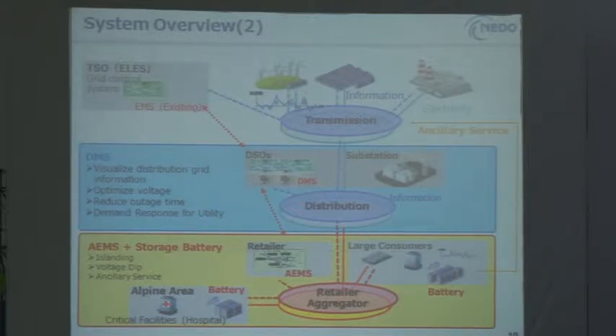As for AEMS, linked with a battery energy storage system installed on the consumer side, AEMS provides 3 services: islanding, which is autonomous operation during grid failure to protect critical facilities against huge power outages; voltage dip mitigation measures; and ancillary service for the transmission system operator. These multiple functions will offer services with more economic benefit to customers.